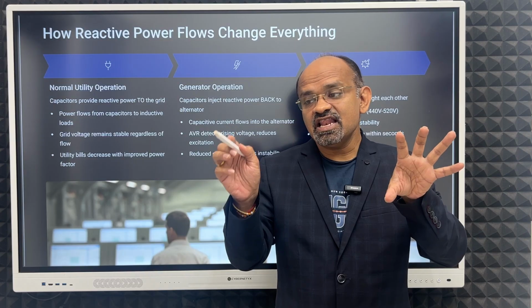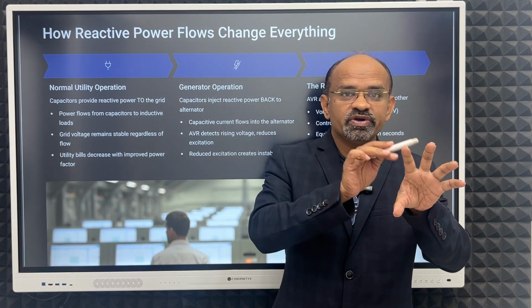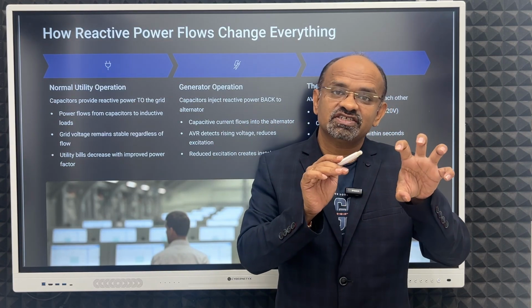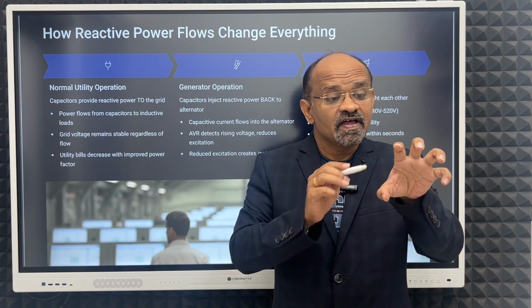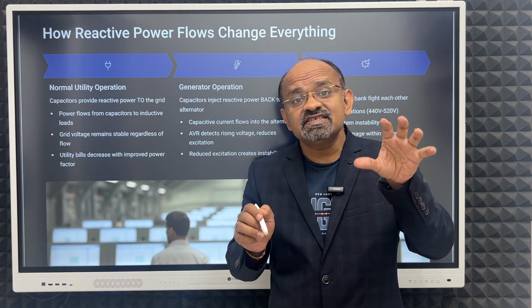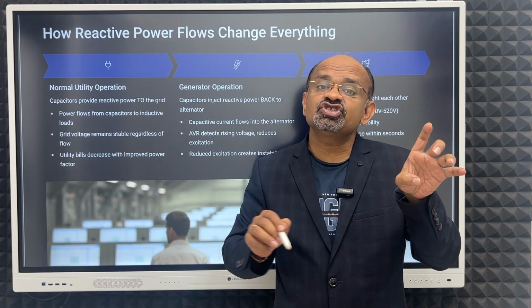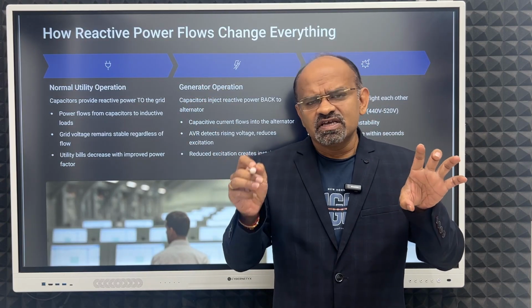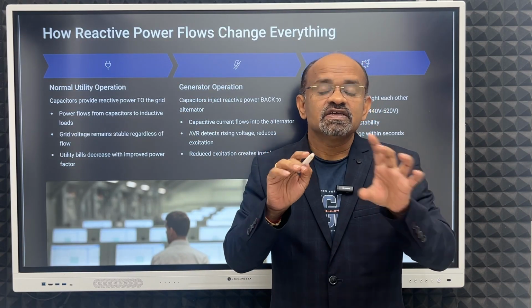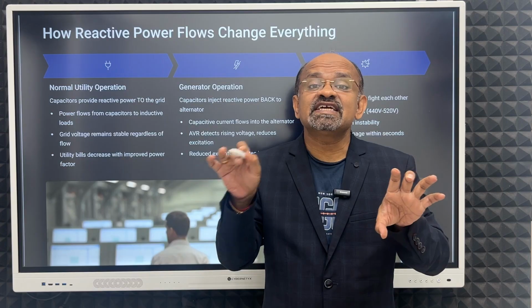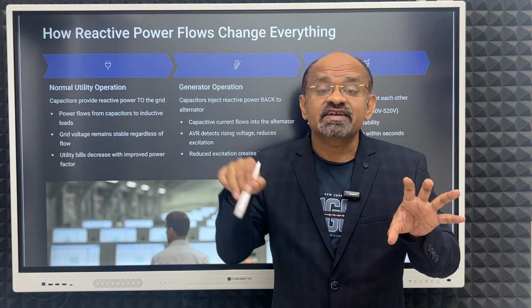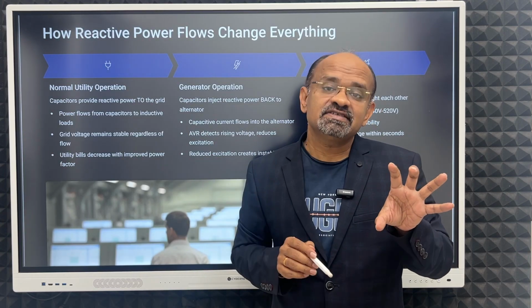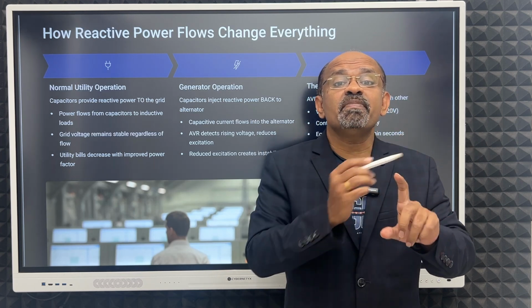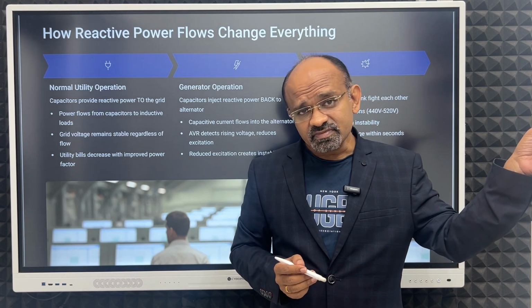Understand this fundamental in detail. In one cycle, the capacitor provides power to the inductive load, so the coil is charged. Inductive load means a coil. In the next half cycle, the coil discharges its magnetism and the capacitor absorbs it. So this cycle keeps happening, and reactive power is compensated inside the circuit, inside our premises. It is not fed back to the utility.